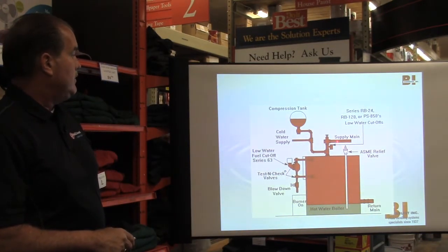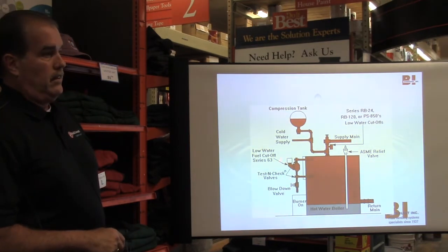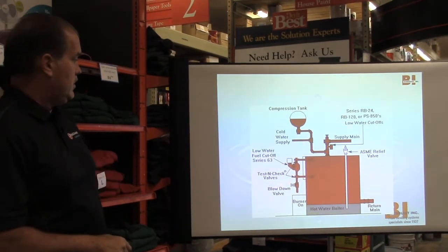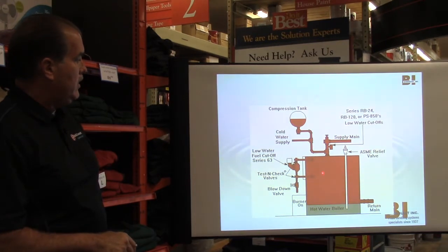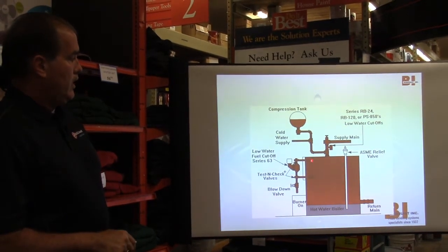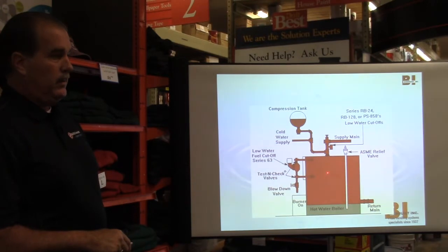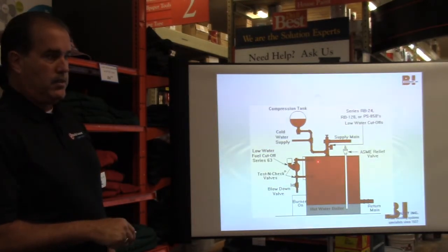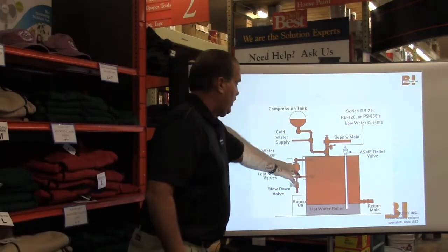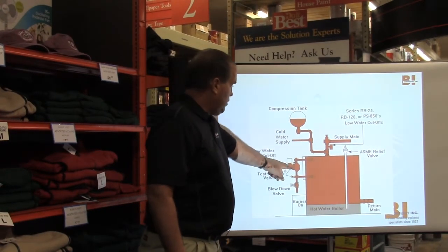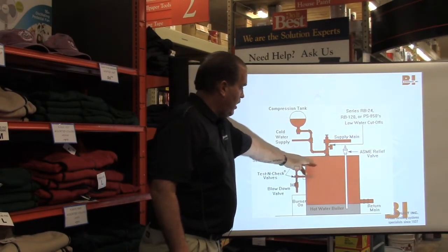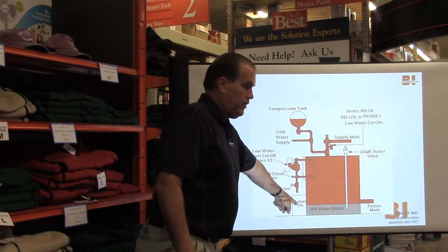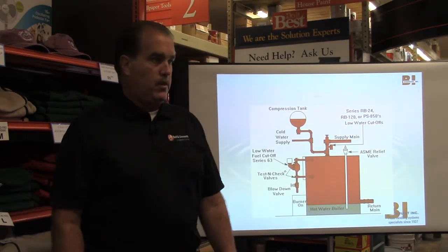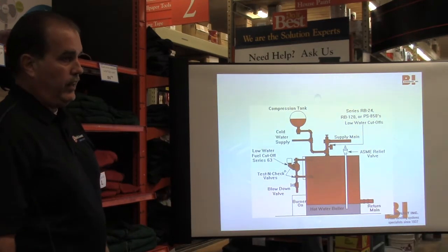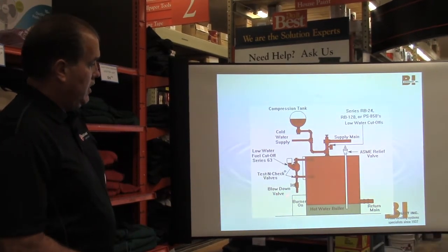So moving on, low water cutoff. A low water cutoff comes in several flavors. This is a float type low water cutoff, and it's piped in so that it knows what level the water is in the boiler. In this case, it's all the way above in a hot water system, so the whole low water cutoff is flooded with water. This one has a float that moves up and down. If the water level drops, the float will drop. It's wired to the burner, and it'll shut off the burner so your burner will not run. It's a safety device. The way you test this is this little blowdown valve. You open this little blowdown valve.